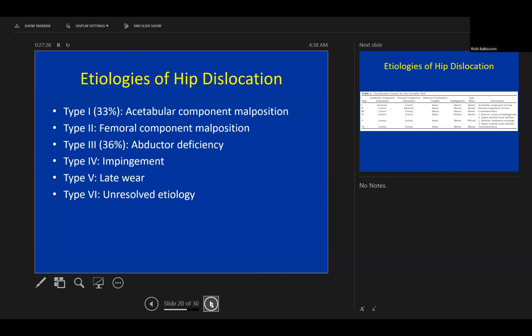And what it can show you here is that determining what is wrong will help us determine what needs to be corrected. And simply put, if the acetabular orientation or femoral component orientation is somehow or another outside of what we would hope for optimal limits, well, then, of course, those components would need to be revised. In the third scenario, where there's normal or appropriate positioning of components, no sign of impingement, but there is dysfunction of the abductors, then the use of a constrained bearing surface may be the only option that we have. In the setting of impingement, then, of course, removing the source of impingement, but adding upsizing of the modular head and liner. And we say that because it has been very well demonstrated throughout various studies, not only in the United States, but throughout the world, that the number one cause of failure or complication occurring following an isolated head and liner exchange is dislocation.